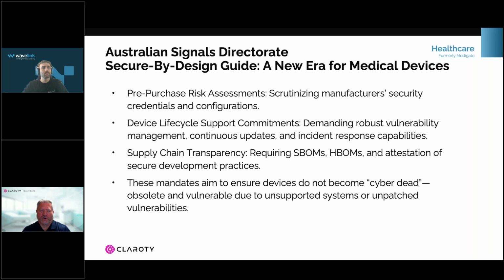The other part of Secure by Design is, over the life cycle of that asset, what do we need to do around making sure that there's vulnerability management, threat intelligence, updates, and incident response? Because the last thing you want is, for example, let's pick an MRI machine, an expensive machine that's probably going to have a 10 to 15 year life cycle. It's not something that you can set and forget, because at some point there are going to be vulnerabilities on that asset, either because of the way it's connected or because vulnerabilities have been found in the underlying operating system that potentially cause risk. So you need to make sure that the organizations selling these devices to you have lifecycle support throughout the journey.